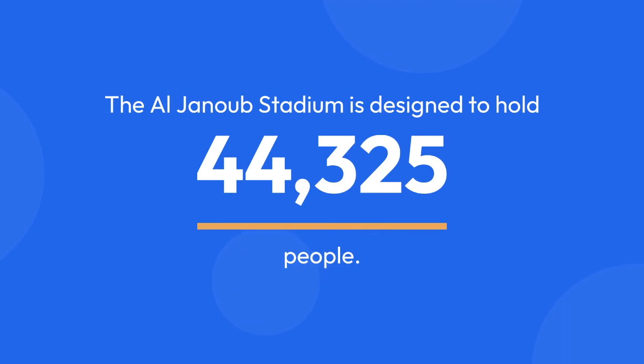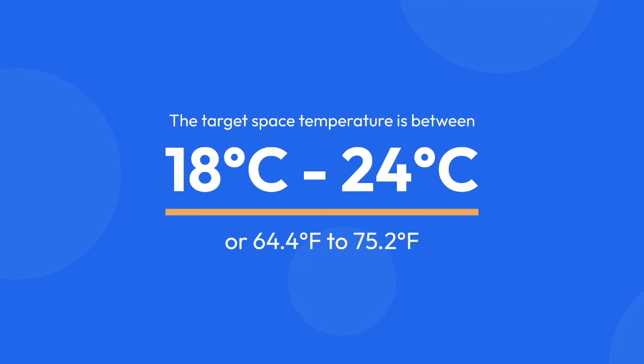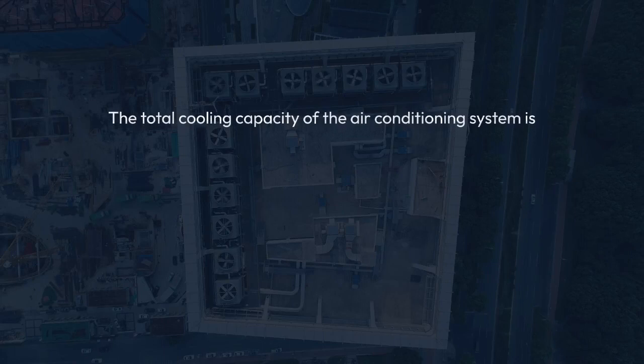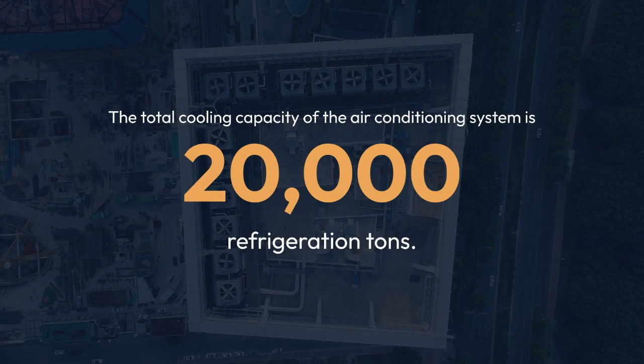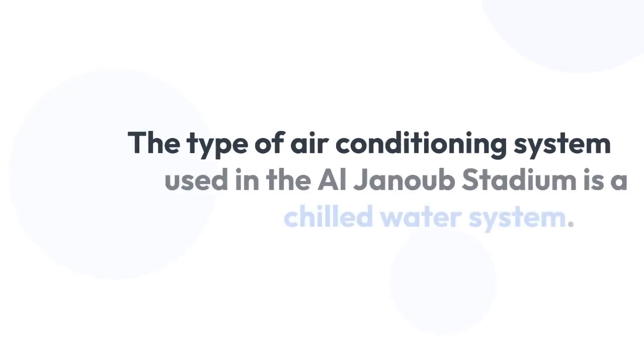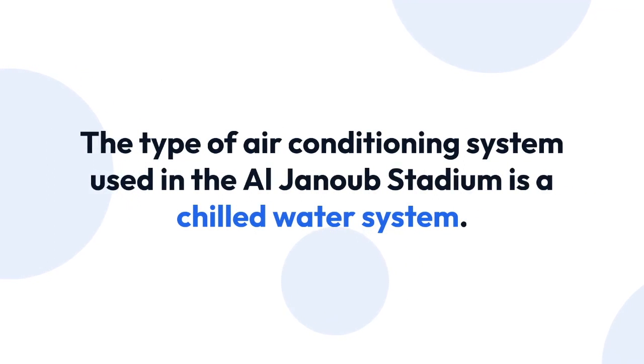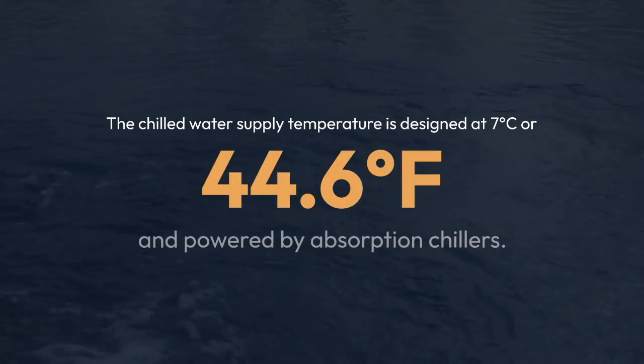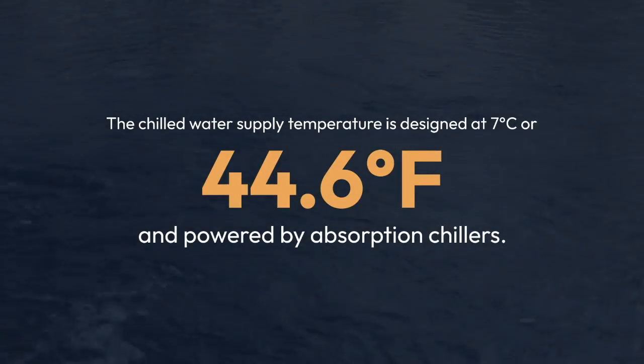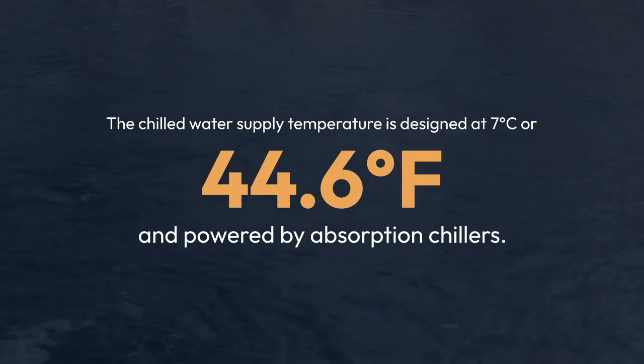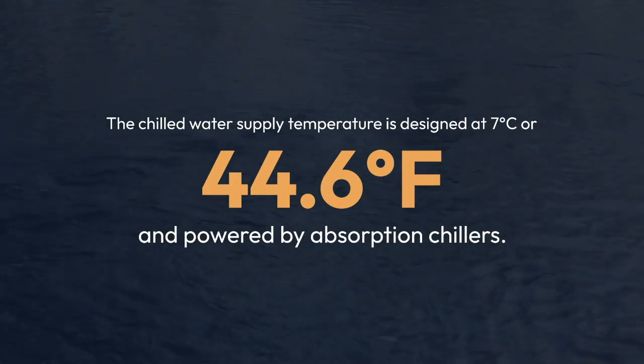44,325 people. The target space temperature is between 18 degrees Celsius or 64.4 degrees Fahrenheit and 24 degrees Celsius or 75.2 degrees Fahrenheit. The total cooling capacity of the air conditioning system is 20,000 refrigeration tons. The type of air conditioning system used in the Al Janoub Stadium is a chilled water system. The chilled water supply temperature is designed at 7 degrees Celsius or 44.6 degrees Fahrenheit and powered by absorption chillers.